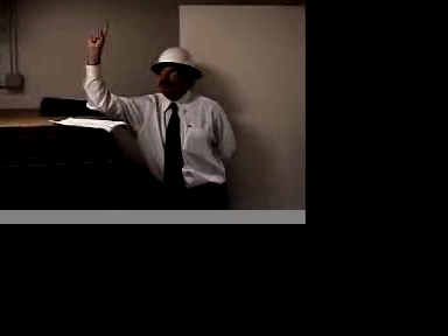Is that in the 3 study rooms, 2nd, 2 and 3 and 4? Yeah, 2, 3, and 4, yes. These ducts rise up in the wall and have an electric heater on them coming off the primary air. So if there's a call for additional heat, those heaters will go on and provide additional heat to those study rooms only. This is exactly what we need for the rest of the units.